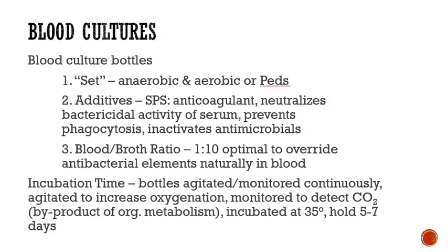So the incubation system takes a baseline reading when you place those blood culture bottles into the instrument for the first time, and then also every 10 minutes after that. So if organisms are present, they're going to produce CO2 as a byproduct as they grow. That is what is detected; there's a gas permeable sensor on the bottom of the bottle. So if there's a change in those subsequent readings, then the machine uses an algorithm to flag the bottle as positive.